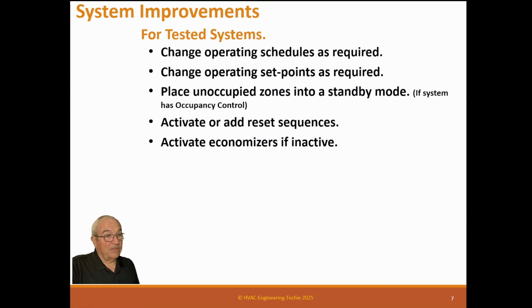And the reason is they get complicated, and when in doubt, if an operator's in doubt, he's going to shut it off. He says if he has any inkling that it's trying to produce more work than it saves, produce more energy than it saves, then he'll close them. And they'll never open them again, so you need to check those out.